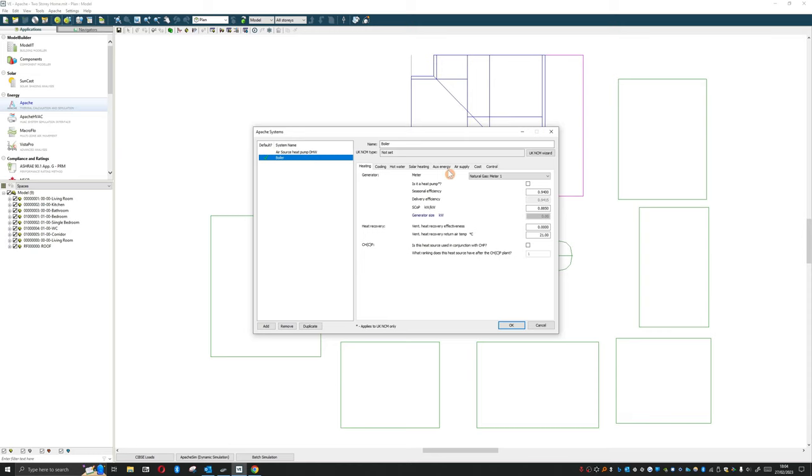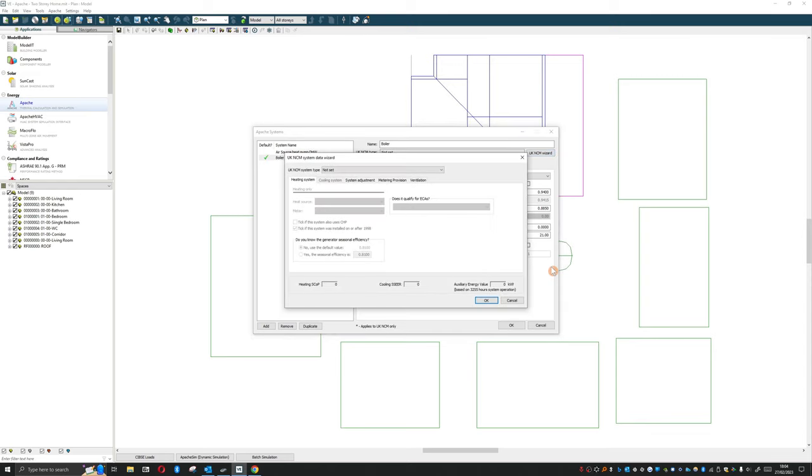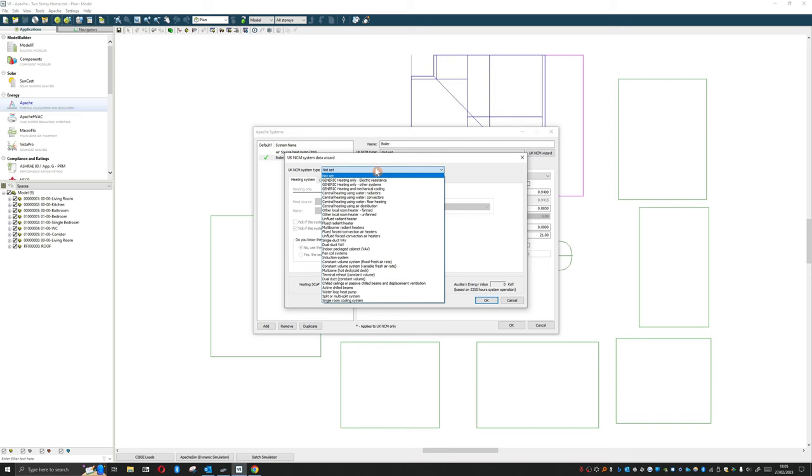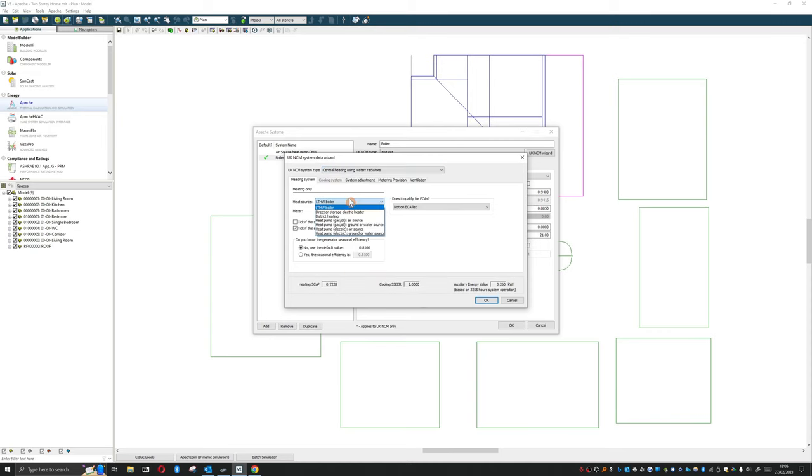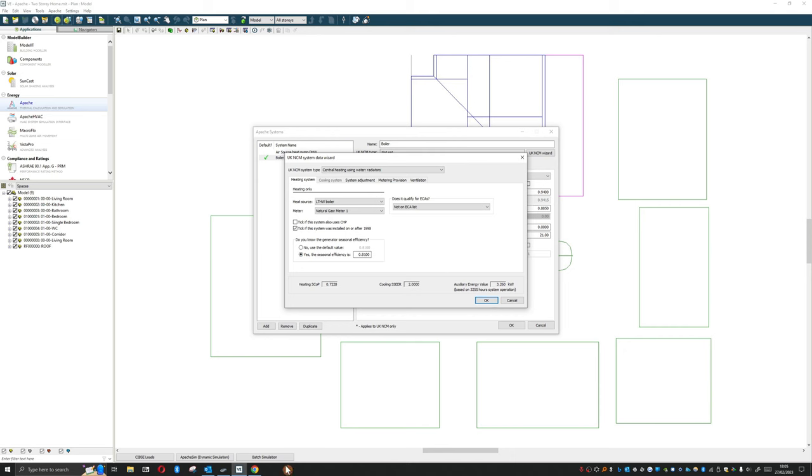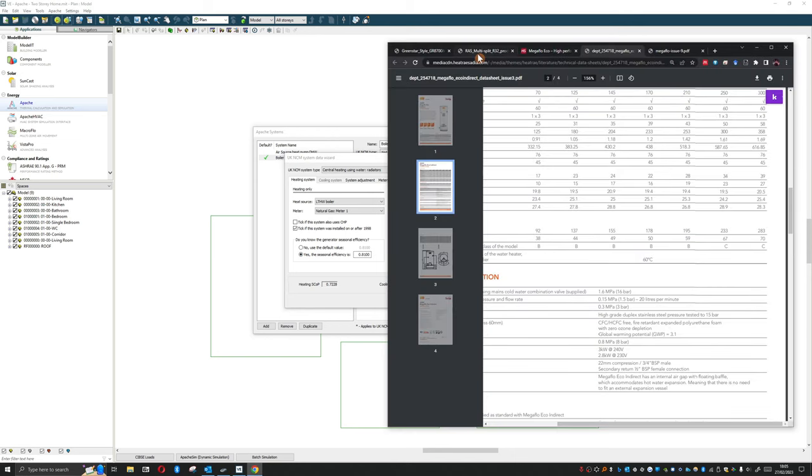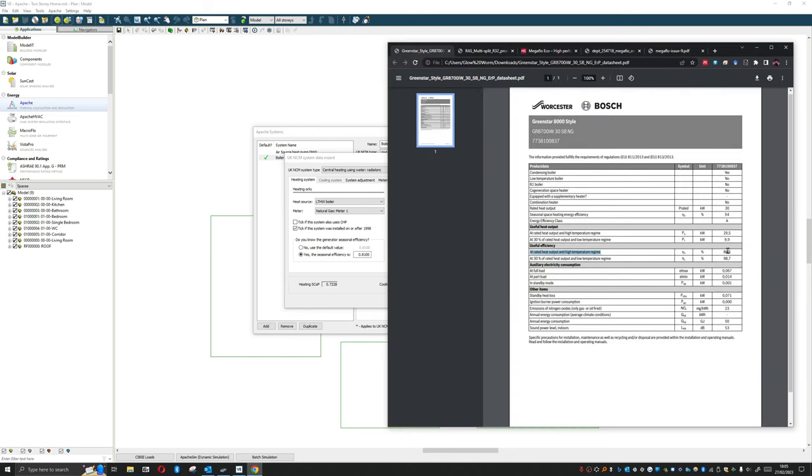Now I did say, what can be useful is if you're very early on in the project and this is a UK based project, you can use the UK NCM types. What this does is it gives you a default set of system criteria that you can use for Part L compliance, or you can just use as a basic system before you start optioneering. It provides a useful baseline. If we hit this, you'll see that there's a lot of different types of systems available. Let's choose something simple - central heating using radiators. It will ask us what the source is. We're going to go with an LTHW boiler. If we don't know what the value is, it will tell us. As it was, we did know what the value is. It was Greenstar, 94%.